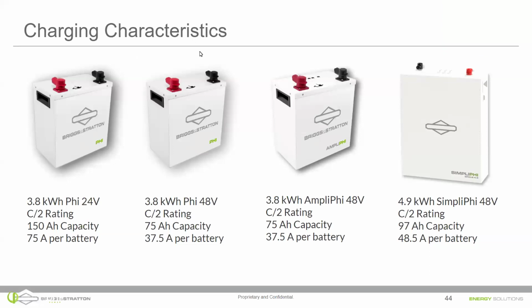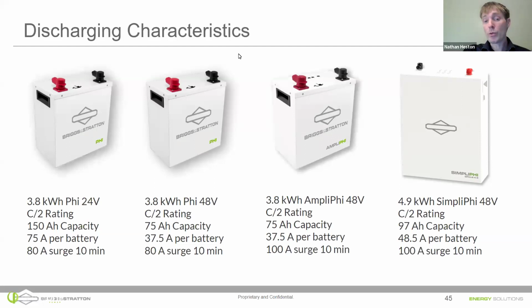I want to build on that. When you say the battery management system will cut off the battery, what do you mean? The battery will open up a disconnect contactor. I have to distinguish that this has not happened with our AmpliPHI and SimpliPHI batteries, our newer batteries, we've never had one of those issues. Those batteries have a more sophisticated battery management system that can protect themselves very effectively. That's another reason we've developed such a comprehensive BMS system, to protect for safety, because that's our number one priority. Great question, I appreciate it.